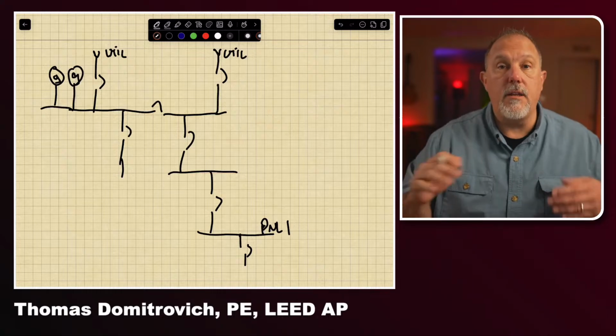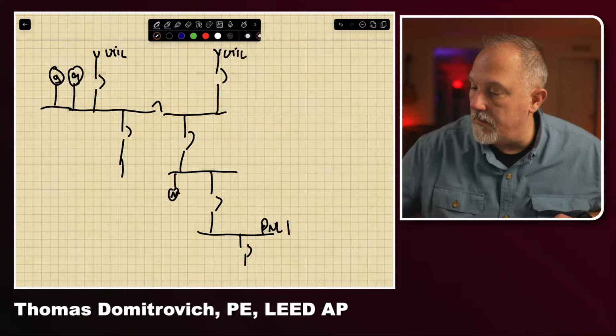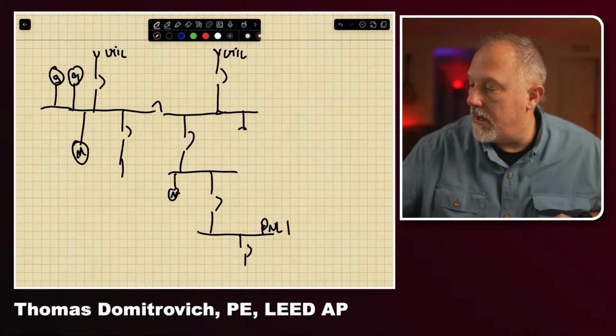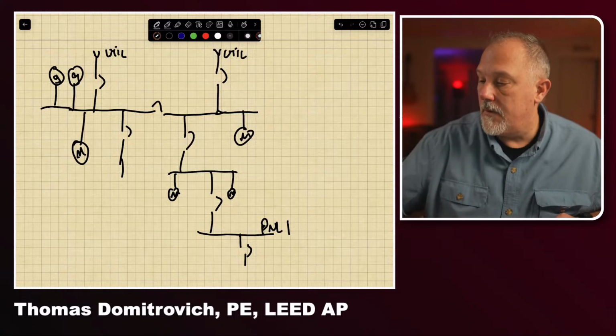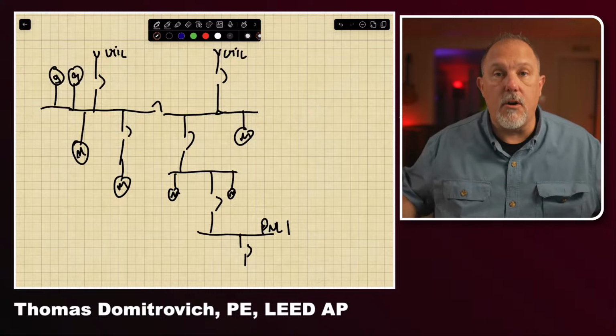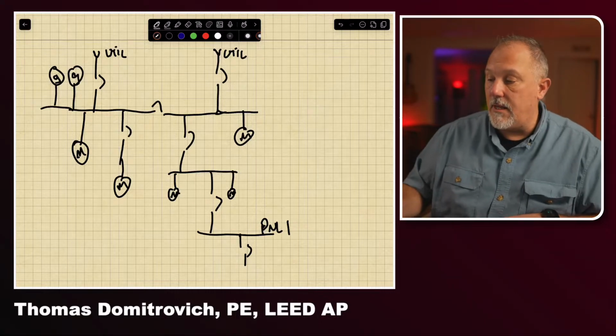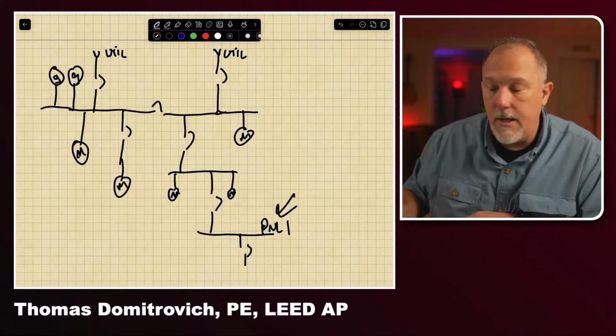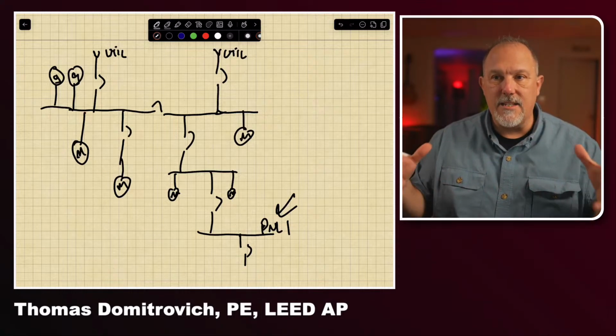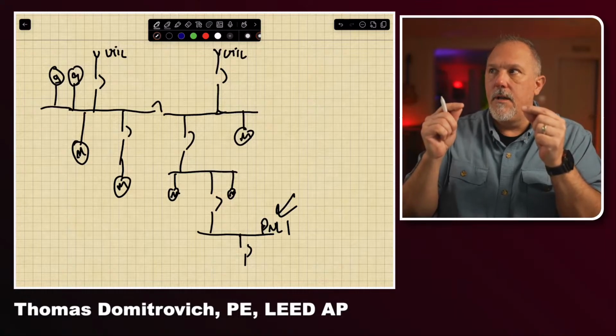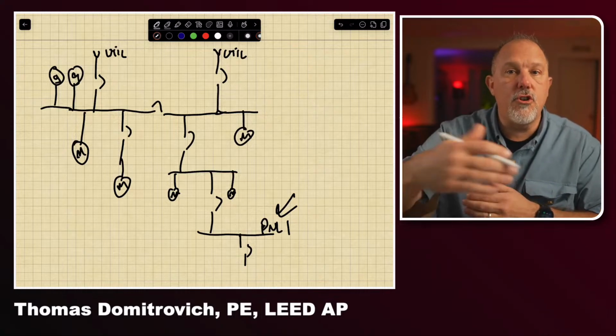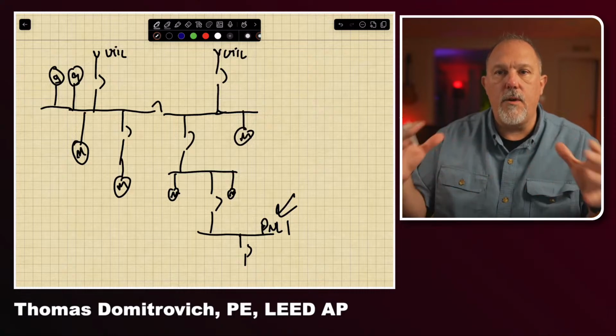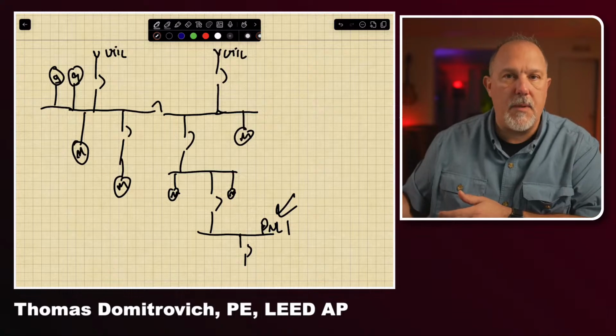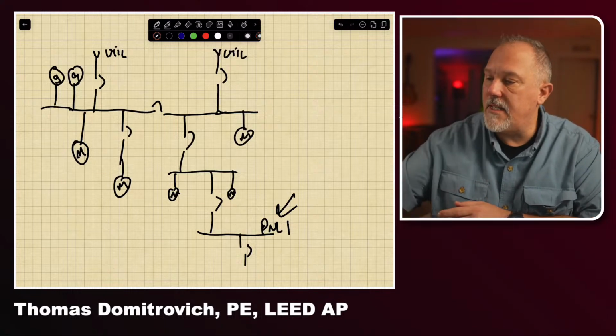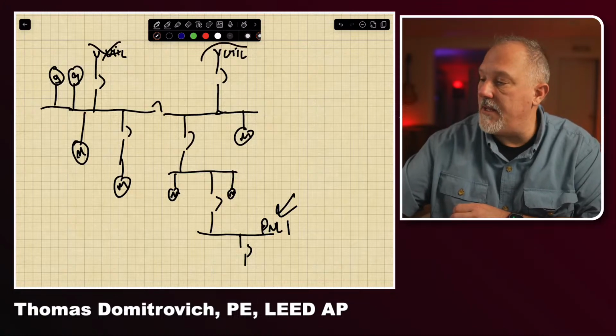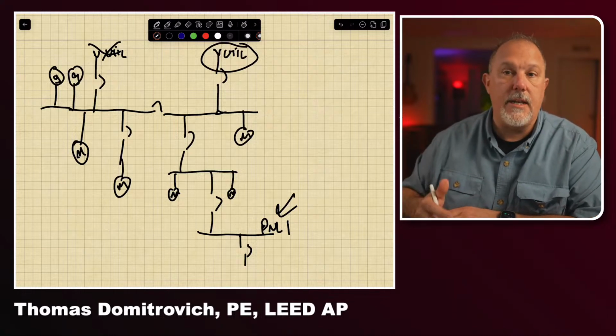Which scenario in the configuration of my power distribution system, and maybe I have motors here too, right? I've got big motors, little motors, and maybe a motor over here. I would have to consider all that motor contribution as well. I would want to calculate the maximum available fault current that I could get at panel 1 and then do my coordination. So the more complicated the system becomes, it's not a challenge of loads other than if those loads are contributing to fault current. My challenge is to determine what configuration of the one-line diagram gives me my most fault current at each of these panels, and then do my evaluations. I might say this is a very weak source. I may do all of my fault current calculations off of that utility source because it is the larger of the two.